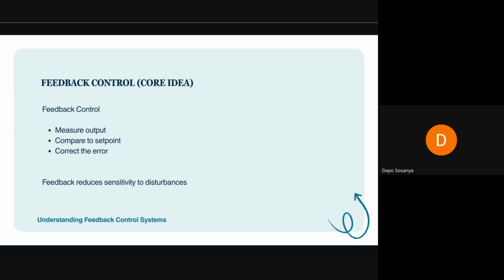It reduces the sensitivity to disturbance. And it takes this action continuously, and that is what we call the scan time. It goes through it continuously. So if your scan time, just for the purpose of explanation, is 10 minutes, of course 10 minutes is not practical, but if it were, you would have disturbances accumulated for 10 minutes before you make a correction. But typical control scan times are measured in milliseconds, depending on how precise you want your operations to be.